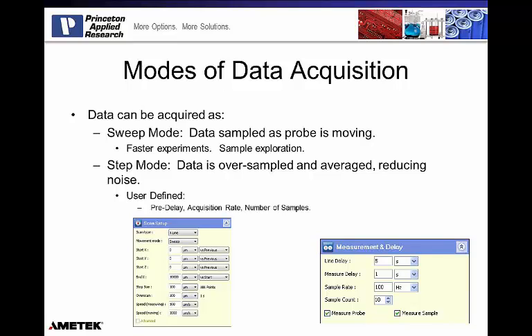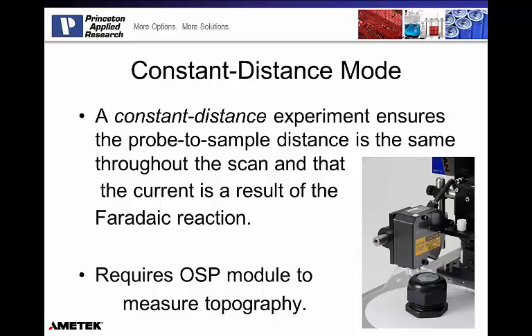So sweep mode, especially for fast experiments, is very valuable if you have a very large sample and we don't know where the activity is happening. It lets us look at a large area in a short amount of time and identify those hot zones to come back to in areas of interest. While most work is done as constant height, there is a very valuable variation called constant distance mode. Where constant height maintained a constant Z position as it increments in X and Y, constant distance mode allows you to make a topographic measurement by some means, and so basically measure the tilt or the curvature of a sample with some complex geometry.